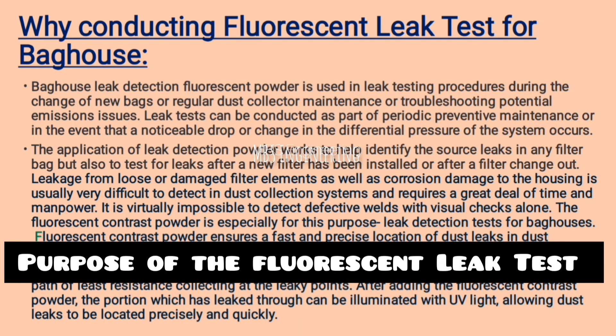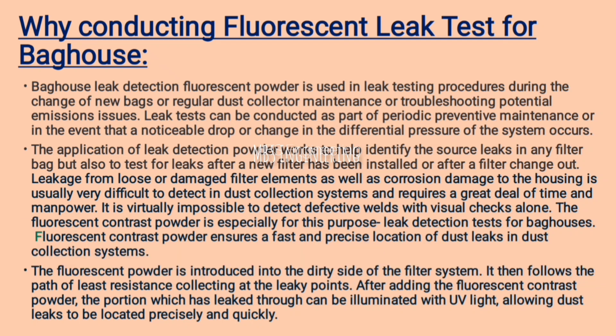To understand why we conduct a fluorescent leak test for bag house: fluorescent powder is used in leak testing procedures during the change of new bags, regular dust collector maintenance, or troubleshooting potential emissions issues. Leak tests can be conducted as part of periodic preventive maintenance or in the event that a noticeable drop or change in the differential pressure of the system occurs.